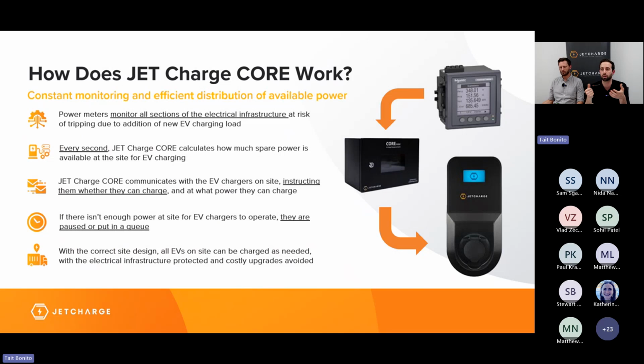So these power meters are constantly recording the power draw at the different sections they're measuring, and they report this data to the JetCharge Core via Ethernet cabling. And as Paul said, this is done on a second-by-second level. So every second, JetCharge Core takes in this data from the power meters and calculates how much spare power is available for EV charging. The JetCharge Core then communicates to the EV chargers and instructs them whether or not they can charge, and if they can charge, at what power they can charge safely. This is also done over Ethernet cabling.